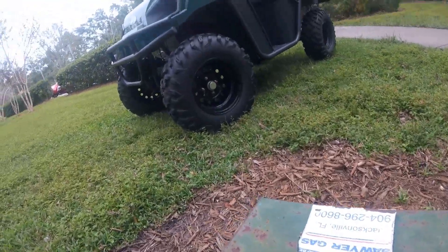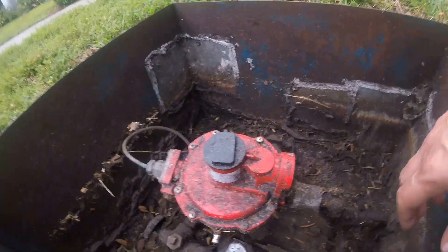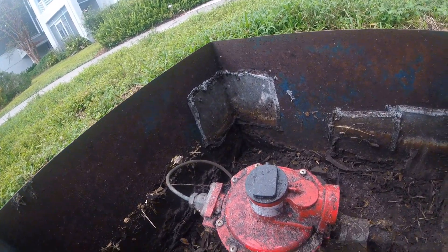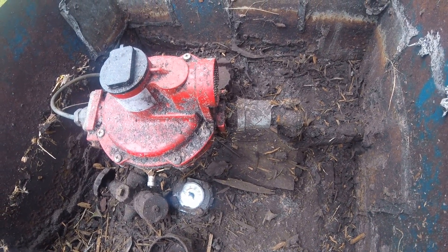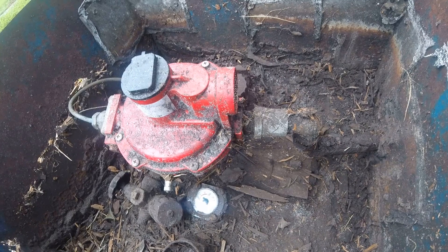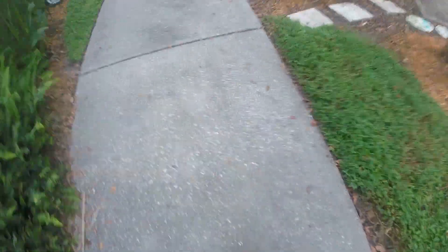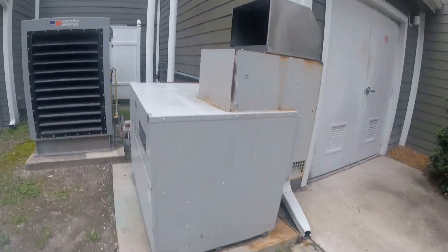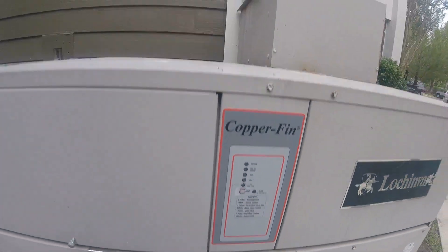One way to figure this out — if you don't know for sure if you've got gas in here or not. There's a magnetic swiper that pulls that needle around. I'm sure we have gas. This is blinking off on low air though — it was giving me a one code. Low air, low air.